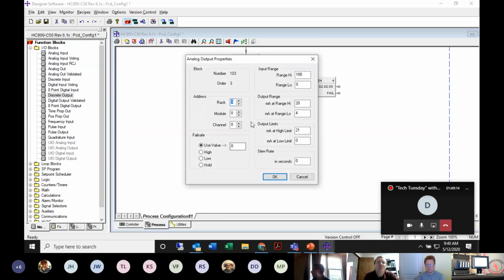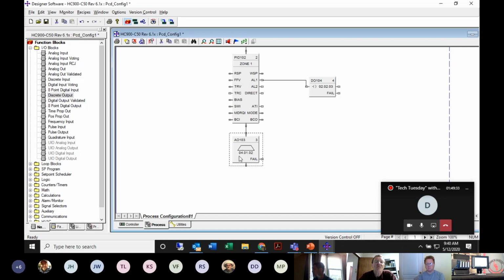Last but not least, analog output. So as an analog output, again, it's a hardwired output, so we have to tell it where it's going to be on the rack. And if we're okay with the 0 to 100% output being 4 to 20 milliamps, then we're good to go. We can hit OK. And again, on that hardwired block, it'll tell you exactly where that hardwire is located.